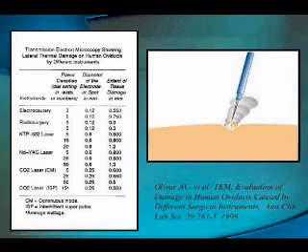If we compare electrosurgery and radiosurgery using similar power densities and a 0.12 mm tungsten electrode, we can see that with electrosurgery we get 1/2 to 3/4 of a millimeter of thermal damage to the wound edge, whereas with radiosurgery we get only about 1/2 of a millimeter, so there is less tissue damage using radiosurgery. Likewise, radiosurgery produced significantly less tissue damage than KTP, YAG, or pulse CO2 laser.